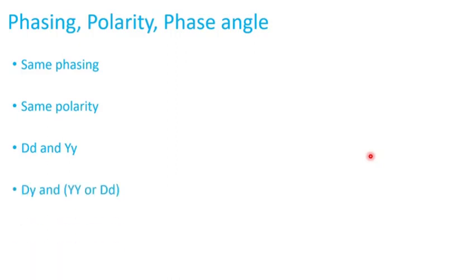If you have delta-wye and wye-wye, or delta-delta, it's not recommended that they are connected in parallel because delta-wye has a 30-degree phase shift. Wye-wye has zero, delta-delta has zero.